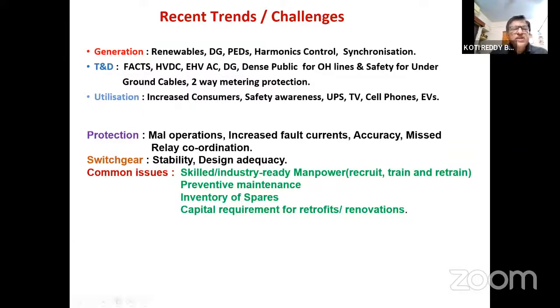On the switchgear side, stability and design adequacy matter. When we add additional local generation, fault current levels increase, and the switchgear may not be able to withstand it. That is also a challenge. The trend is to go for new equipment, but maintaining the stability of the switchgear is a very important issue.